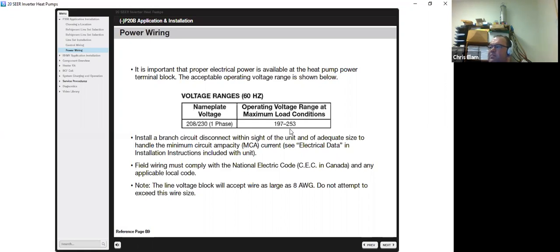If you're operating at 249, 250, and you spike past 250 on a regular basis, you will end up with inverter faults pretty consistently. If you get down below 197, you will also have faults. They will try to protect themselves because they'll sense those voltages and try to fault out. But if you get enough spikes in the proper way, you will damage the drive board.